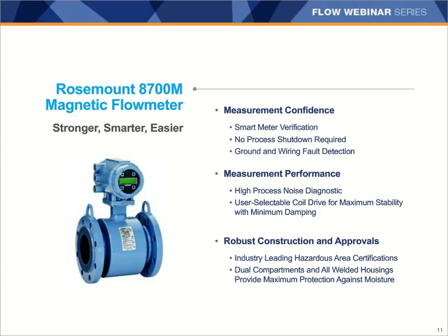As you probably know, one of the most common causes of flow measurement errors for magnetic flow meters is improper grounding. The grounding and wiring fault detection that is available on the Rosemount mag meters monitors the entire frequency spectrum to recognize if AC noise is affecting the flow reading and alert you if it is.